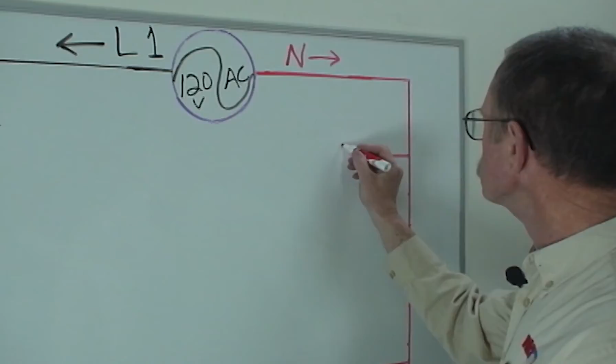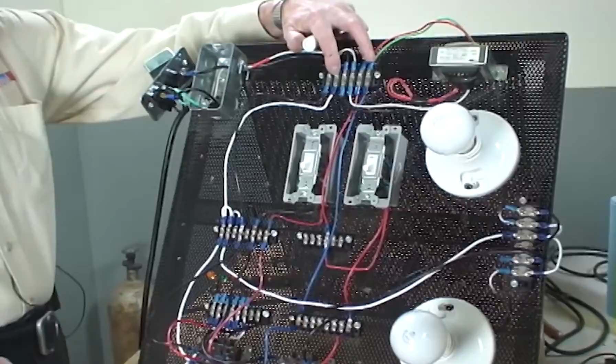So I'm just going to go out here a little ways and label it relay coil 1. You can tell it's 120 volt because it's plugged right into one side of neutral. That's as far as I'm going to chase that because I'm concentrating on the neutral side at this point in time. Notice it came down from here, so this point where the wire comes in off the extension cord and this point are exactly the same - there is no difference. So it could be anywhere on this side of the schematic.